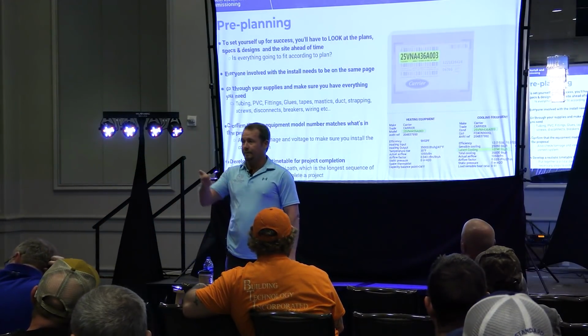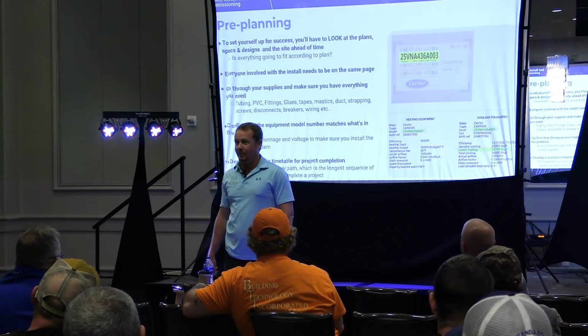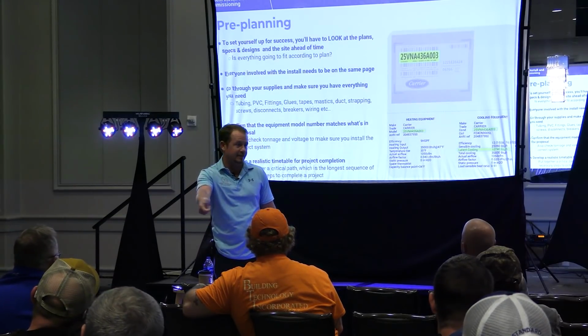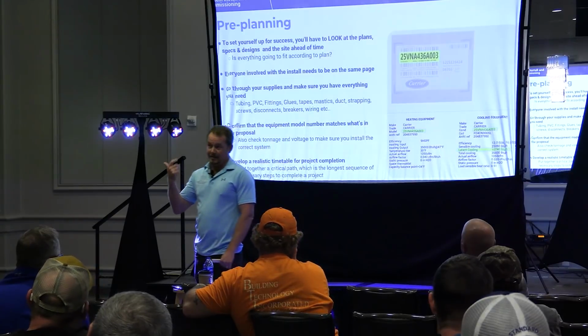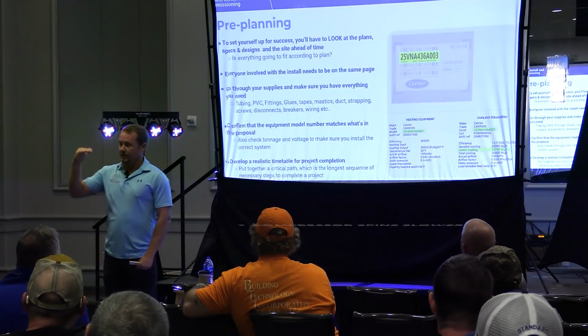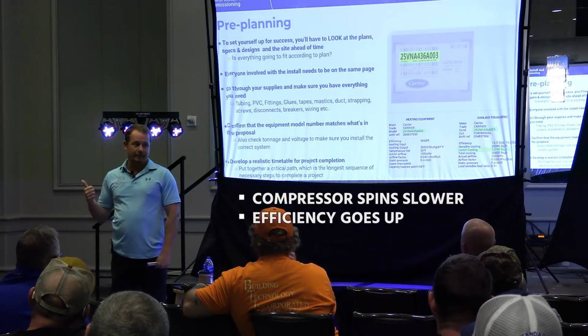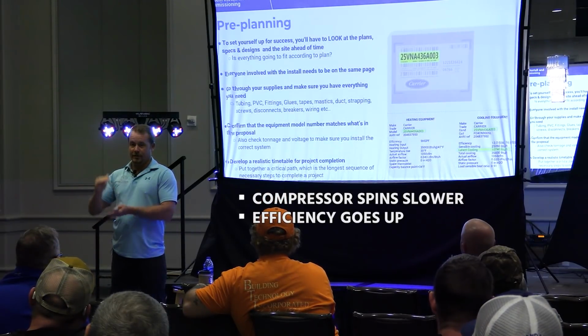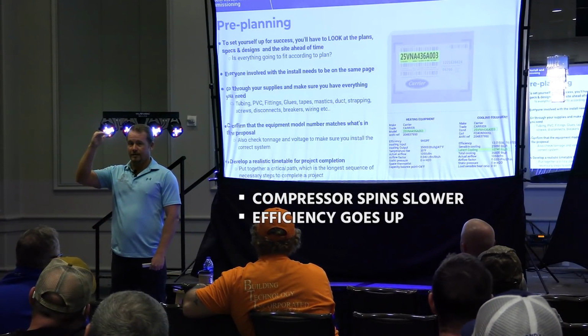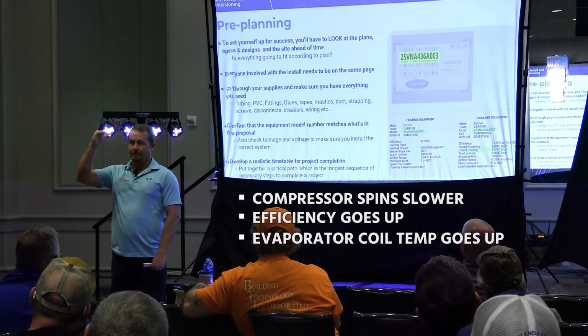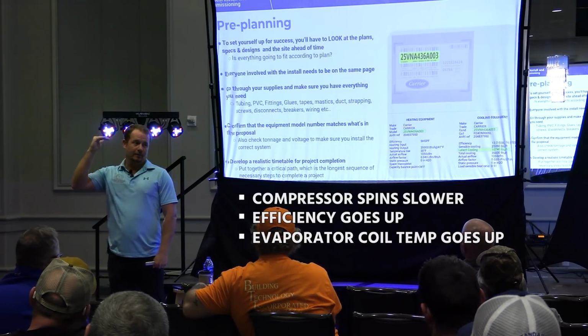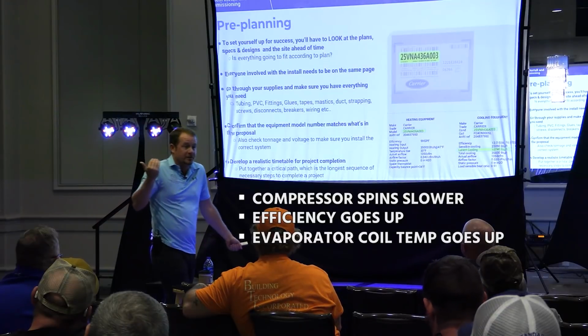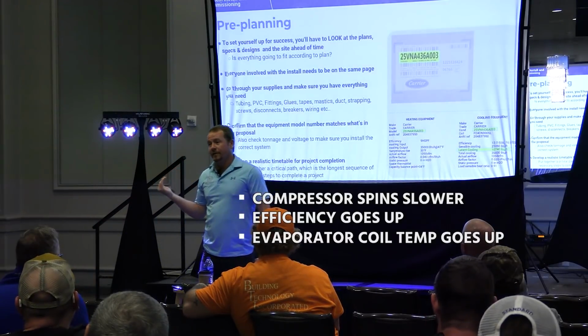And the customer can go ahead and jack that thing up to high speed all the time if they want, right? Oh, I want it to cool better, put it to high speed all the time. So what happens if that's the case? Compressor spins slower, efficiency goes up, but when the suction pressure goes up, what does the evaporator coil temperature do? Goes up. You get a warmer evaporator coil. Is that good or bad? It's good for efficiency. It's bad for dehumidification.